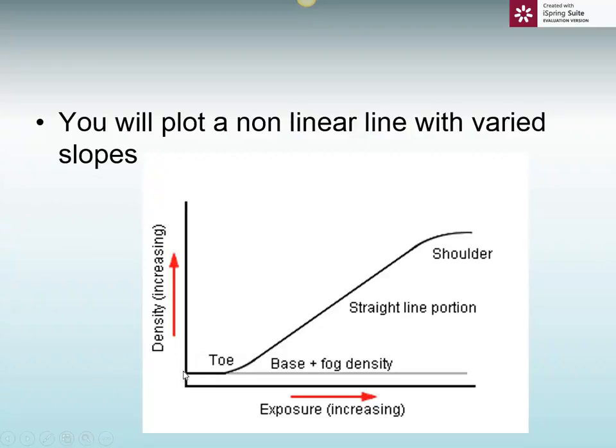When you first do the manufacture, you're never going to measure zero. First of all, keep in mind the film has that blue dye in it. That blue dye is going to absorb some light, so we're now at a non-zero state. At the same time, when they put the emulsion on the film, there's going to be a certain amount of residual left. They might call it fog. It might happen during the manufacturing process. It might happen during the transporting process. It just might be old. What you're going to get then is what's called base plus fog, and that means we're going to be in a non-zero state here at the toe. It will never reach zero.